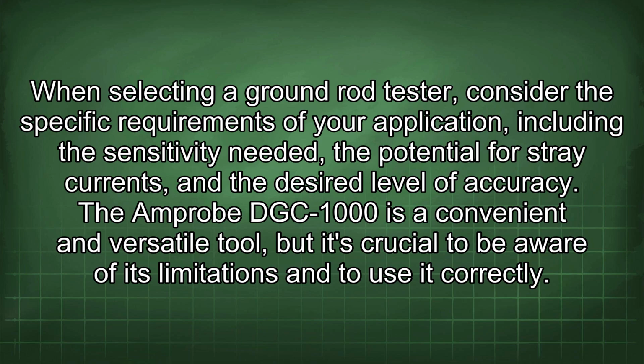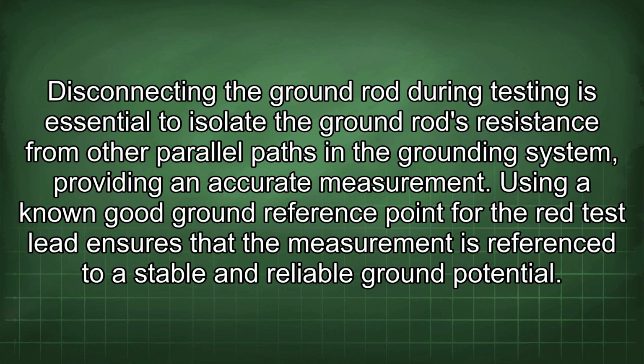When selecting a ground rod tester, consider the specific requirements of your application, including the sensitivity needed, the potential for stray currents, and the desired level of accuracy. The Amprobe DGC-1000 is a convenient and versatile tool, but it's crucial to be aware of its limitations and to use it correctly. Disconnecting the ground rod during testing is essential to isolate the ground rod's resistance from other parallel paths in the grounding system, providing an accurate measurement. Using a known good ground reference point for the red test lead ensures that the measurement is referenced to a stable and reliable ground potential.